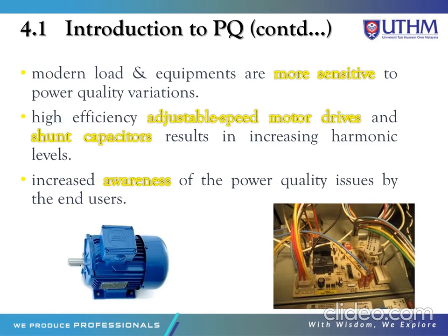Next, there are some loads that contribute to power quality variation. The first is that modern loads and equipment are more sensitive to power quality variance. The second is that high efficiency adjustable speed motor drives and shunt capacitors result in increased harmonics levels. So we have to increase awareness of power quality issues among end users.